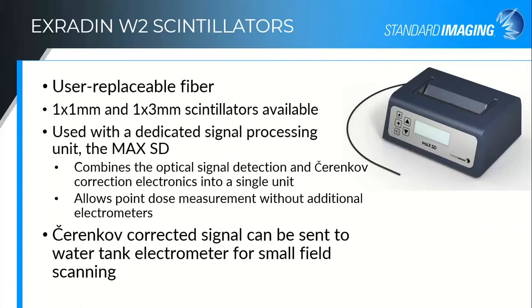The second generation device is called the W2. It has multiple fibers and is used with a dedicated optics and electronic system called the MaxSD. We provide the system with both a one by one millimeter scintillator and a one by three. For extremely small fields, everyone wants the one by one because it's a uniform size — you don't have to worry about volume averaging over the three millimeter length, and you can use it in any orientation. The one by three, however, gives you a direct connection to all of the W1 publications that came before because the fiber is identical — the same geometry, same size, same everything.